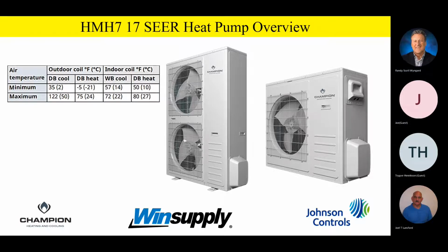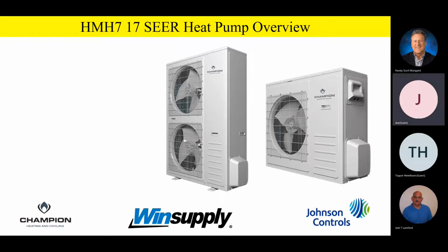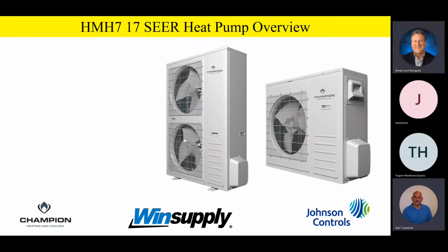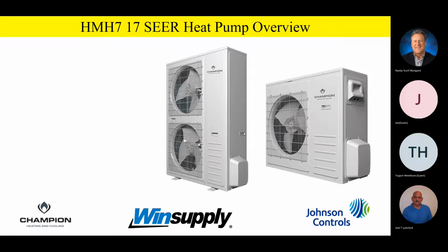Okay. Does that automatically come back on then when it gets back to -5 or -4? Yes, it will. All the field reports I've had is that's basically a point where the outdoor unit senses that it's not going to be able to make heat, but once the temperature rises above that, it resumes normal operation. That is correct. Good question.